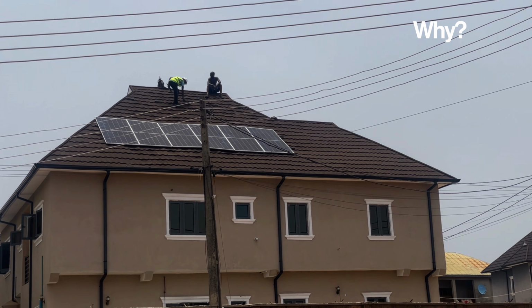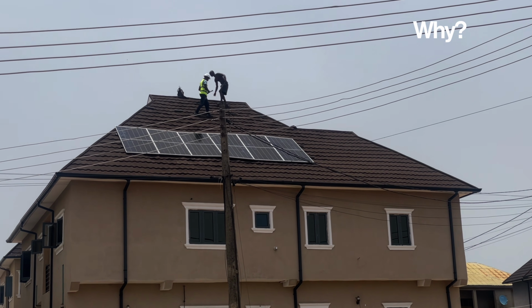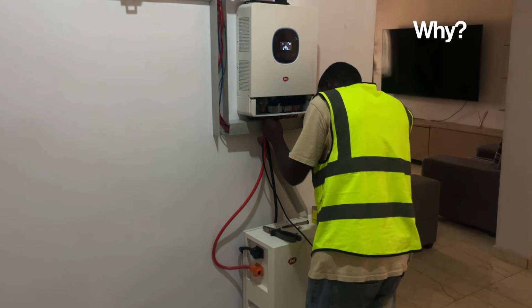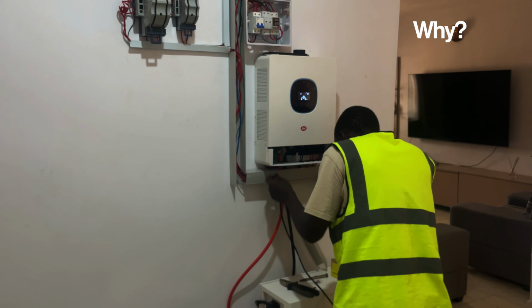So obviously, when you're dealing with big batteries like that, you need to get a large inverter. You can't be using a 3 kilowatt inverter, because what inverter means is the things you can switch on together at the same time. It's not just about your battery, it also depends on your inverter. Since I got a 6 kVA that can handle surge up to 8 kVA, I switch on everything all at once. I can use up to 2,000, 3,000 watts in terms of the stats.